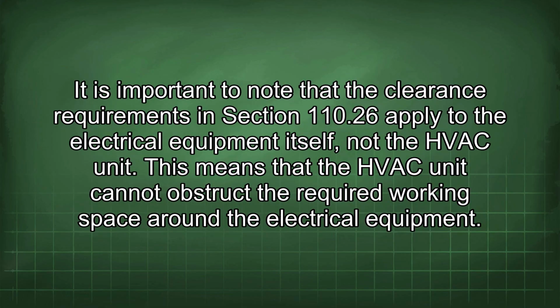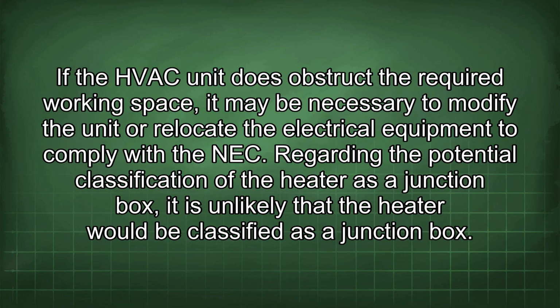It is important to note that the clearance requirements in Section 110.26 apply to the electrical equipment itself, not the HVAC unit. This means that the HVAC unit cannot obstruct the required working space around the electrical equipment. If the HVAC unit does obstruct the required working space, it may be necessary to modify the unit or relocate the electrical equipment to comply with the NEC.